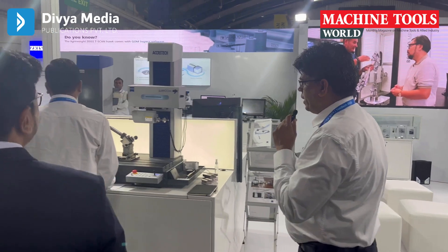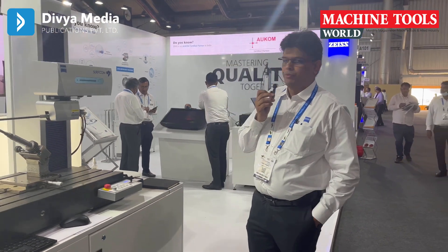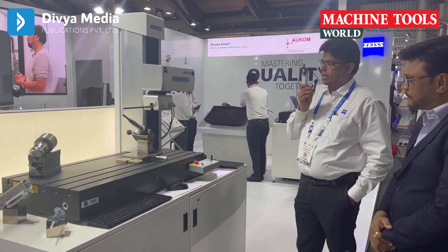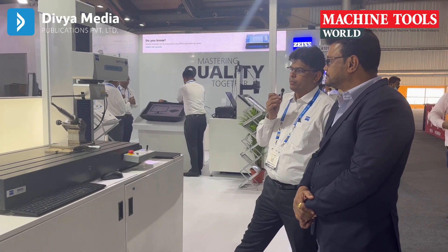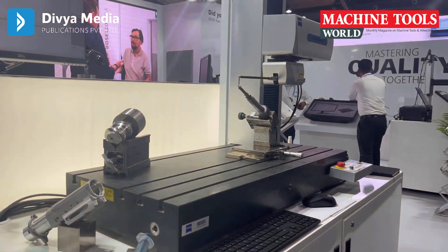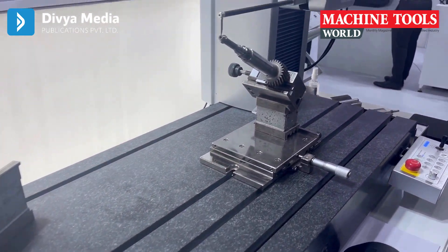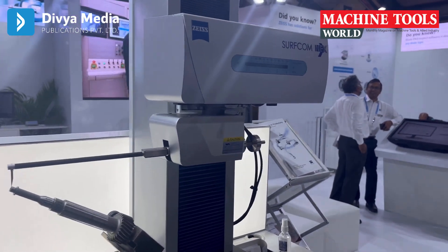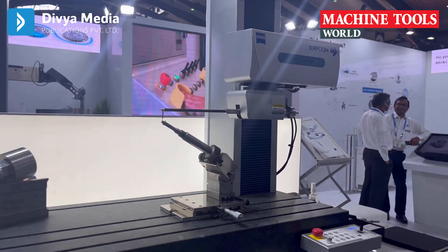Here we have the Surfcom NEX, which is a combination of surface roughness and contour measuring station. The USP of this product is its wide contour range, making it quite useful in the bearing industry or in any shaft or metal cutting industries where super precision in roughness and contour is required. This product is already available in the market with more than 1,500 installations — very successful. The brand name is Surfcom — surface roughness and contour measuring station.